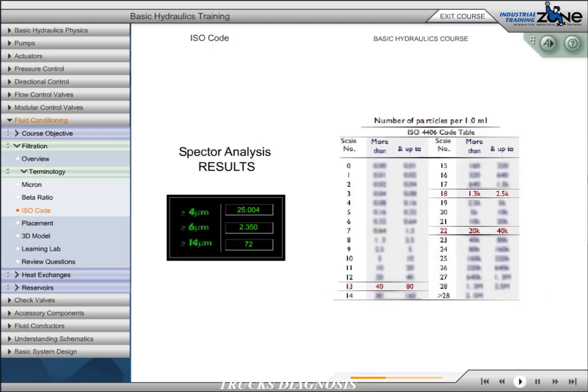To interpret the meaning of these results, a graph like the one shown would have been consulted. In this example, a rating of 22, 18, 13 indicates the following. The first number, 22, indicates that the number of particles greater than or equal to 4 micron in size is more than 20,000 and less than or equal to 40,000 per milliliter. The second number, 18, indicates that the number of particles greater than or equal to 6 micron in size is more than 1,300 and less than or equal to 2,500 per milliliter. The third number, 13, indicates the number of particles greater than or equal to 14 micron in size is more than 40 or less than or equal to 80 per milliliter.